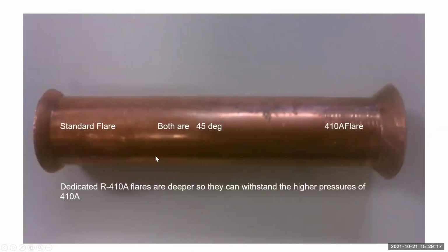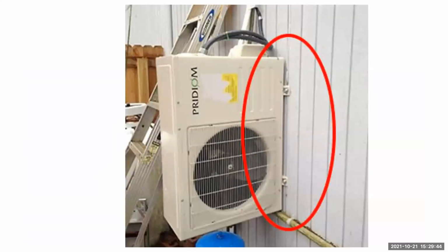So here's the difference between the standard flares like they used in R22 or even the old gas lines. I'm sure there's still some of those out there. So you can see a distinct difference between the R22 and the 410A flare. It's almost double the size, and this is done so it'll handle higher pressures. So I like to put this in there. It looks like they got it mounted pretty good. I think they're probably going to have an issue with oil return.